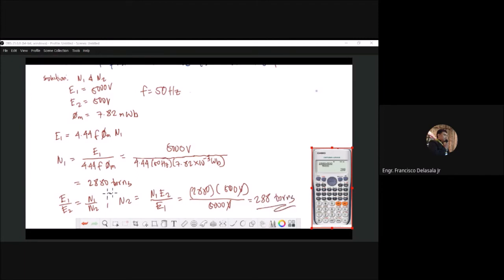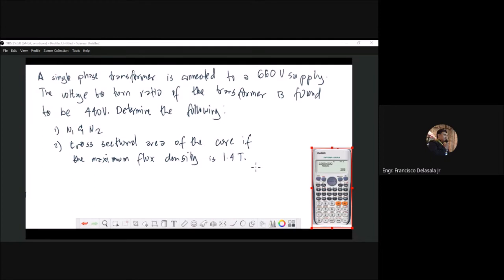So 288 turns is the answer for the secondary winding and 2880 turns for the primary winding. Now we have a second problem: a single-phase transformer is connected to a 660-volt supply. The voltage-to-turn ratio of the transformer is found to be 1.1 volts per turn. We need to determine the primary and secondary turns and the cross-sectional area of the core if the maximum flux density is 1.4 Tesla.